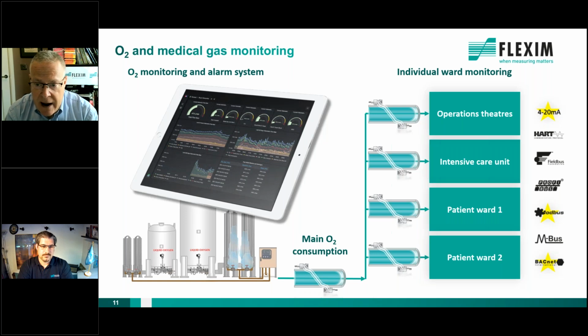Now, obviously, we have outputs from the meters. That's anything from a simple 4 to 20 milliamp to various buses. I think probably the most common we've done in hospitals has been BACnet, but there has been Modbus. And then that data can be delivered to an oxygen monitoring and alarm system. In some cases, that's part of the building management system of the hospital. In other cases, it's a standalone oxygen monitoring system.